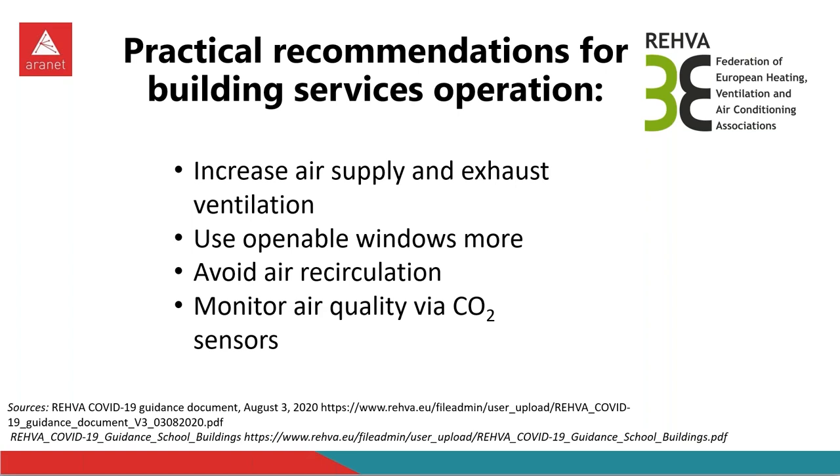Whereas in several offices that have these small conditioning units, they don't actually pull in the air from outside. They just recirculate and cool down the existing air. And the case here is that this type of system is actually worse than no ventilation at all, because it is recirculating the same air that has been there already. If there are any contaminants in the air, it keeps them there longer and doesn't let these virus-containing particles settle on surfaces. So having a recirculatory ventilation system is actually worse than no ventilation at all.